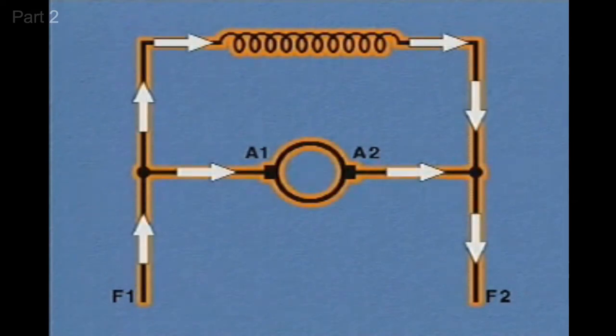If full-line voltage were applied to a shunt motor that did not have resistance installed in series with the armature, the resulting high current flow could severely damage the armature.